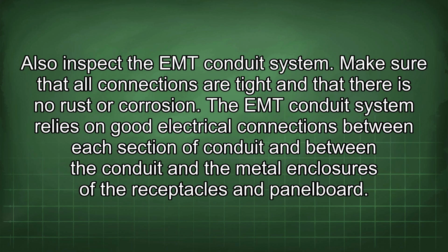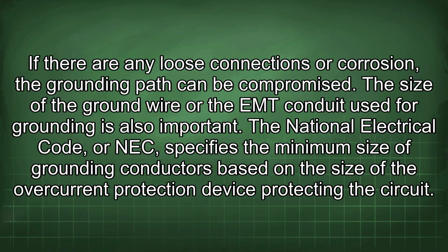Also inspect the EMT conduit system. Make sure that all connections are tight and that there is no rust or corrosion. The EMT conduit system relies on good electrical connections between each section of conduit and between the conduit and the metal enclosures of the receptacles and panel board. If there are any loose connections or corrosion, the grounding path can be compromised.